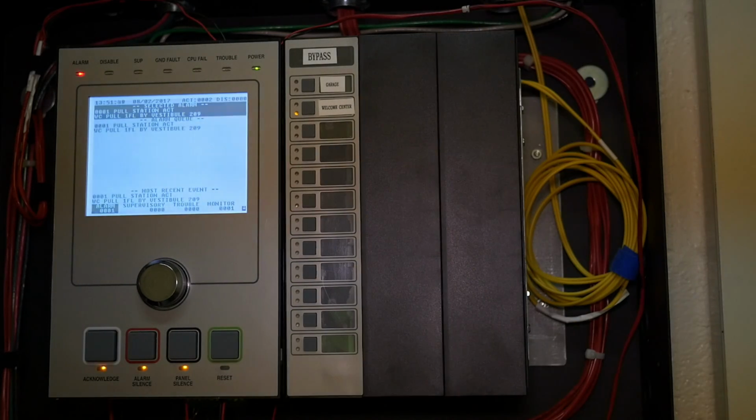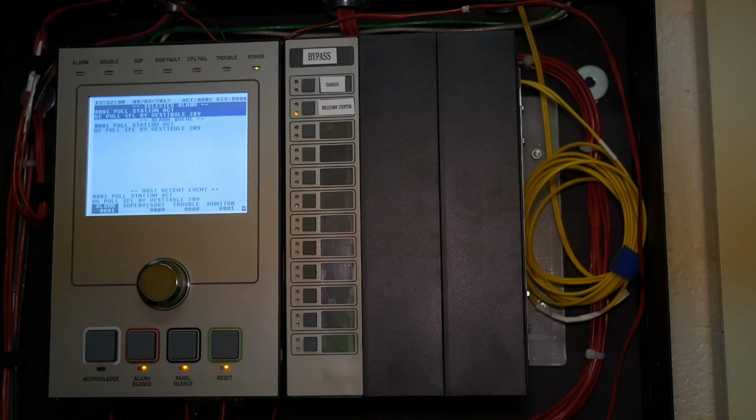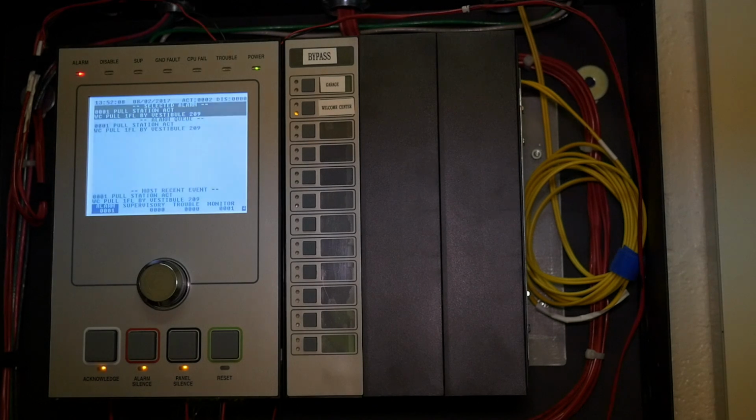And once you figure out, hey, someone pulled the pull station, no big deal, it was an accident, or if it was a smoke and it's a false alarm, you can come down and reset. You could do the restart, but this is what the reset is for, to reset devices that are out in alarm. Now, if you reset this and this doesn't clear, say with a smoke detector, you'd have to physically go to that smoke detector and look at it. It would be flashing red, a red LED, if it was still in alarm, and you'd have to fan it out or clean it out of some sort. Again, don't take devices out while they're in alarm, because it's not going to get it out of alarm. You're still going to have to put it in and fan it out. That's the only way around it.